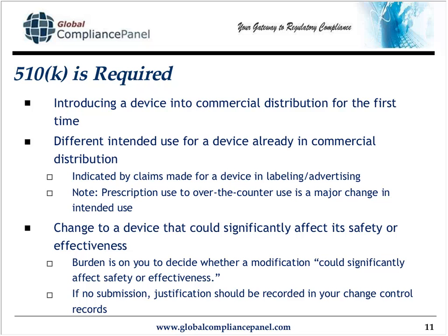An example is changing a device from prescription use to over-the-counter use. I'm absolutely changing the intended use from only doctors can prescribe this or use it to anybody can. That's a major change in intended use that will require a new submission.